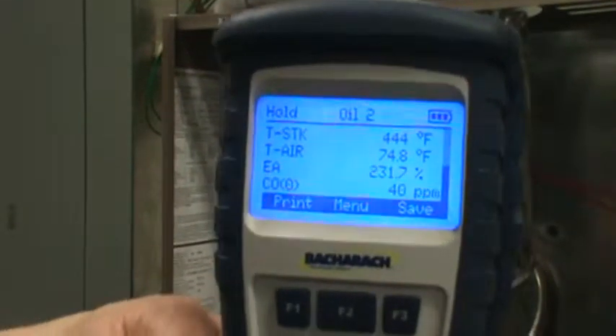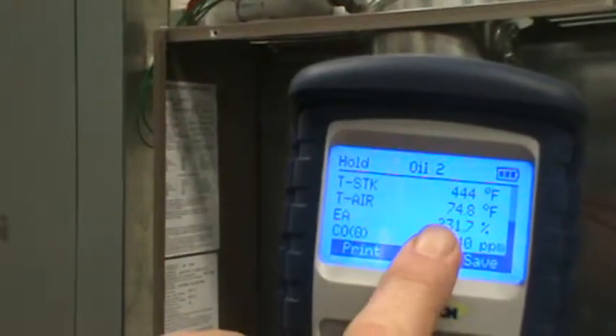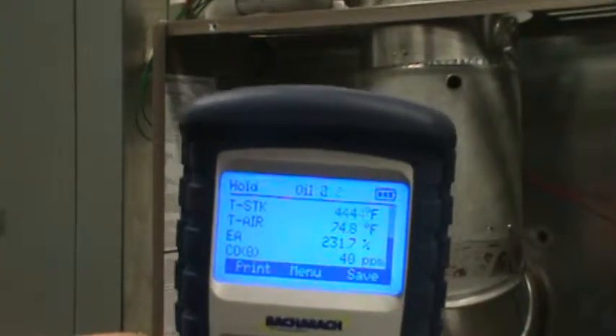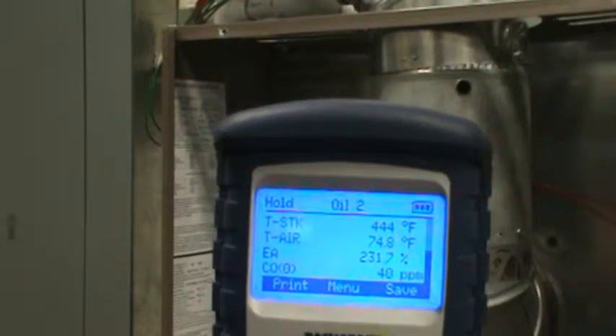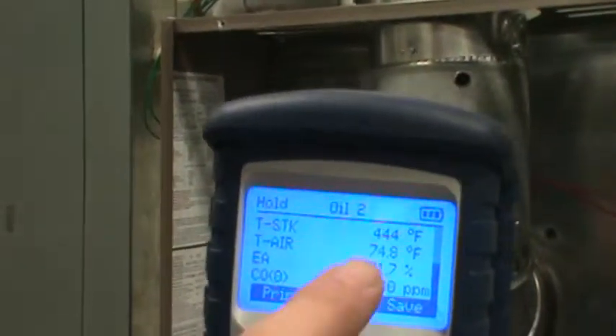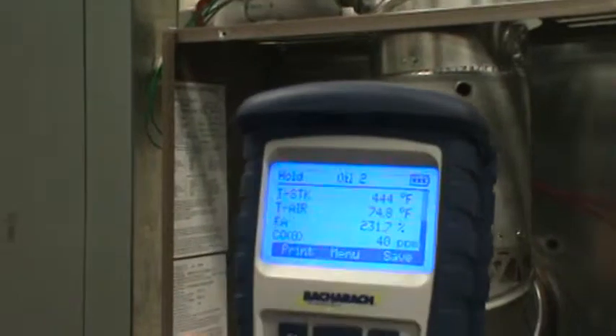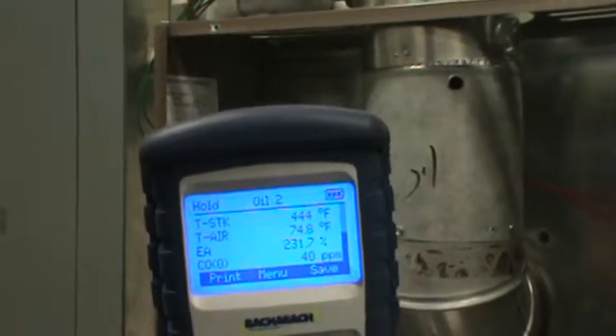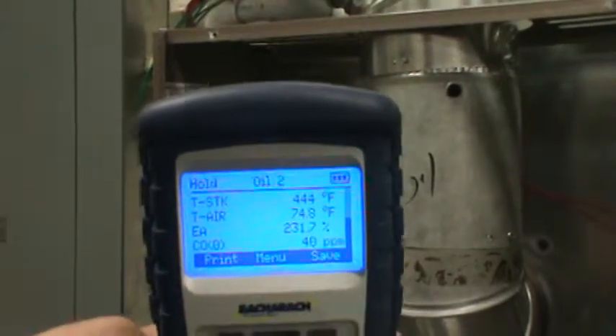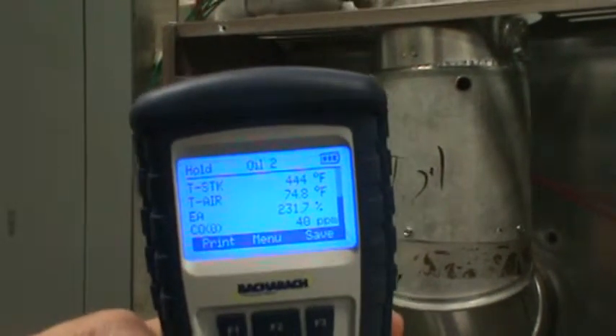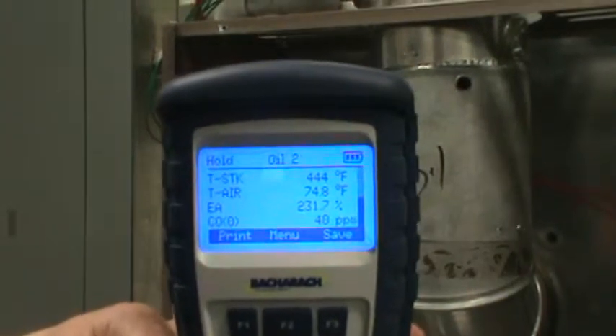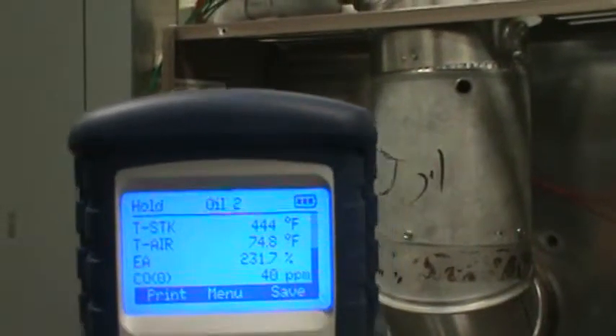But the problem is we're introducing too much excess air. And what that's going to do is that's going to cause the flue gases to move very fast through the heat exchanger. And we're going to lessen our contact time. And when we lessen the contact time, you can see we're getting 444 on my stack temperature, my net stack temperature. That puts my gross over 500, which is a little too high. It's too high. That's another warning. So that's another sign saying, hey, you know, you have too much excess air. We want to try to get that excess air down. Remember, we want to get our excess air down to the point as minimal as possible so that we don't have these values.